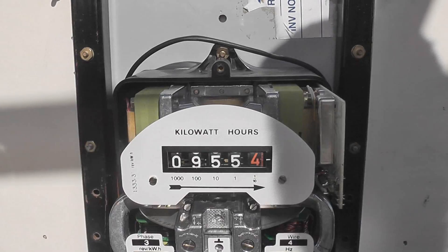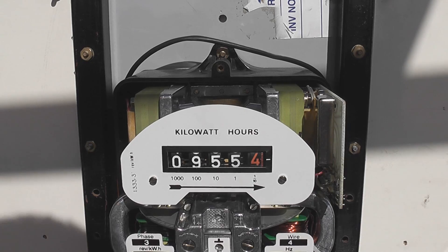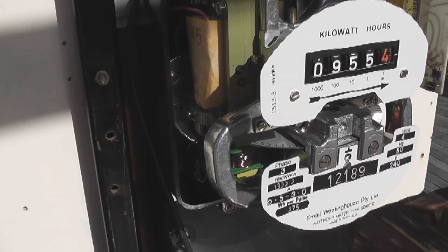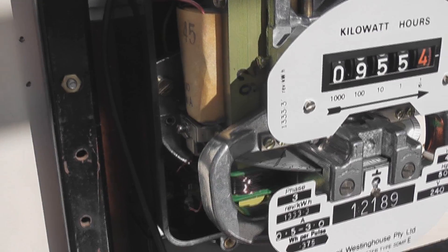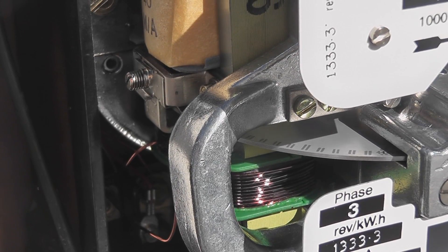I've got more of these meters so it's not the end of the world. This was definitely a case of severe overload. Yeah, there you go — it's a bit overloaded here. That coil has been very hot. That's what happens when you overload a coil.